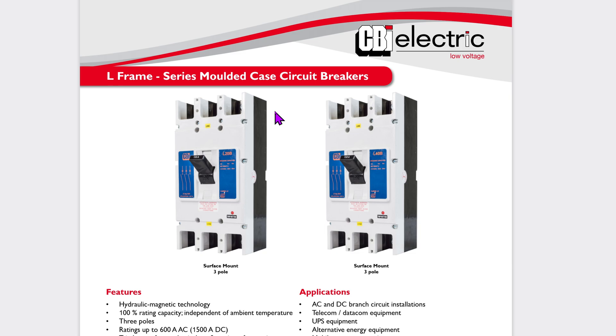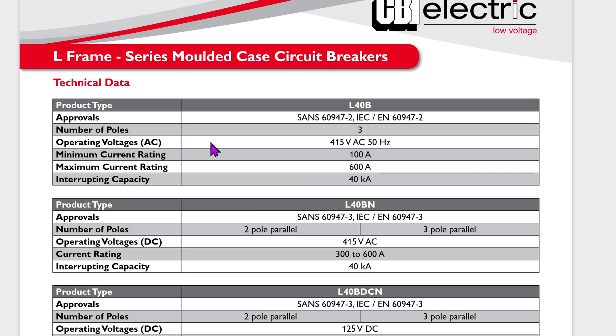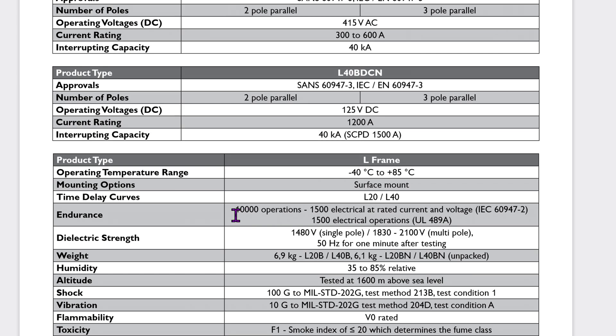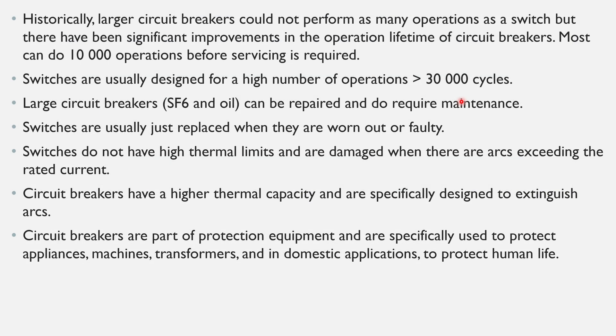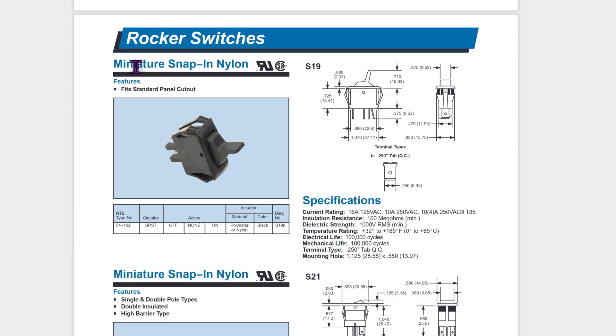When choosing circuit breakers, you can view the specifications and see the number of operations available. For example, this circuit breaker which can handle a maximum current of 600 amps can offer 10,000 mechanical operations, 1,500 of which are at rated current. Switches are usually designed for a high number of operations exceeding 30,000 cycles.